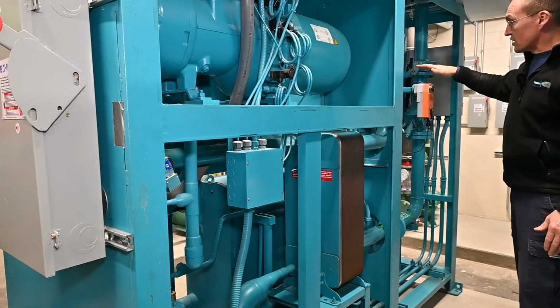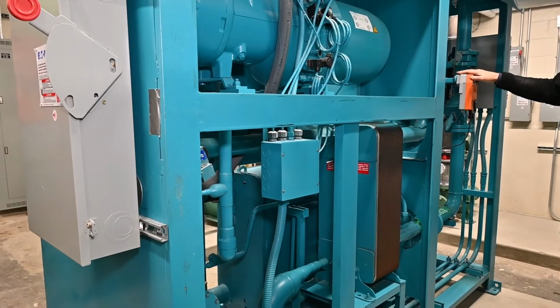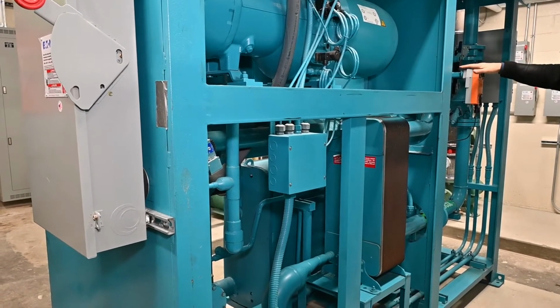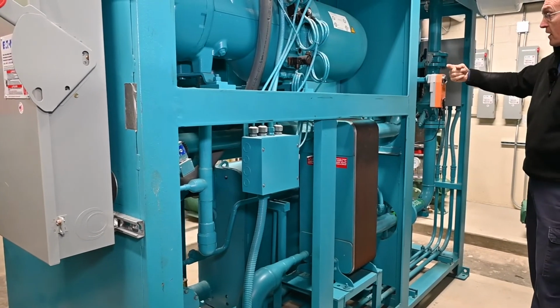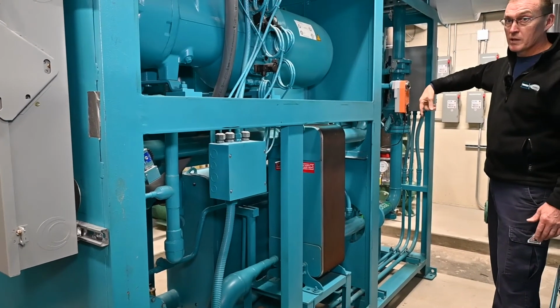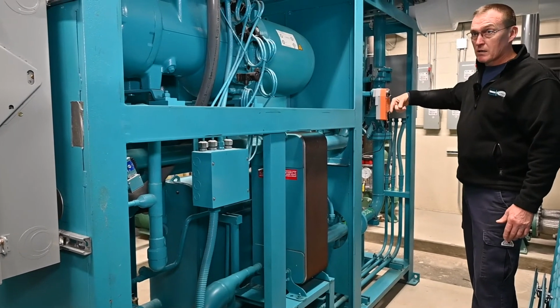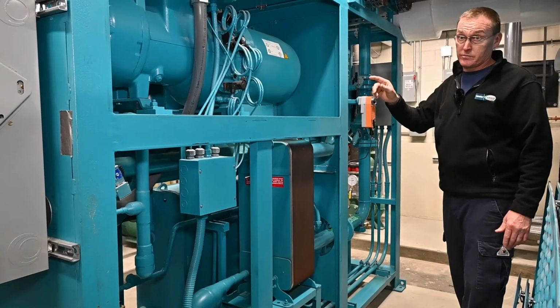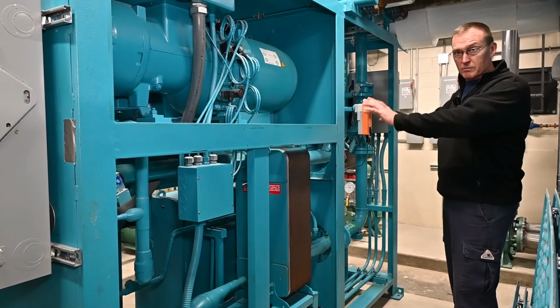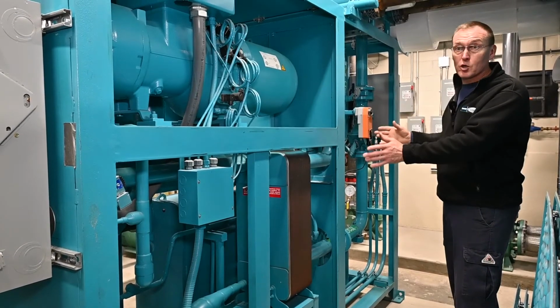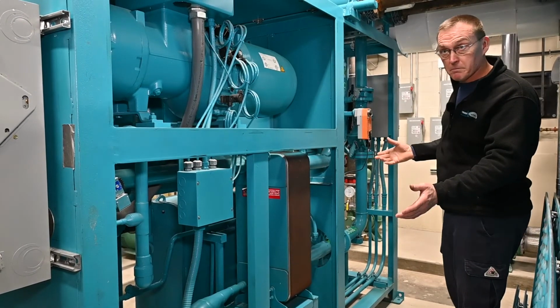You're going to then see this Belimo valve on the warm glycol side open. Now this valve has a 2.5 minute stroke, so it's going to take 2.5 minutes to go from closed to full open. At a minute, the compressor will start. That helps us with discharge pressure and everything else, especially on a cold start if you've been off for a long period of time.